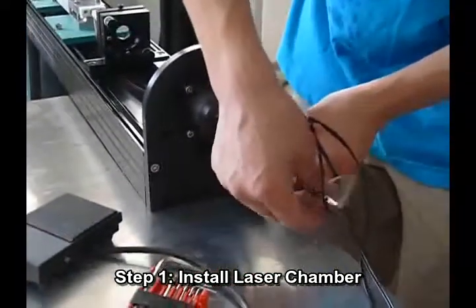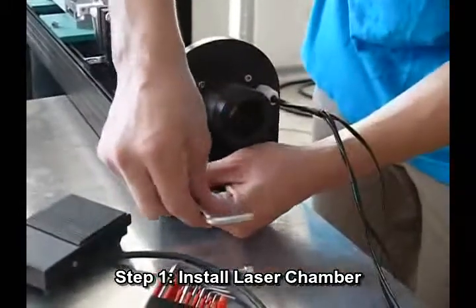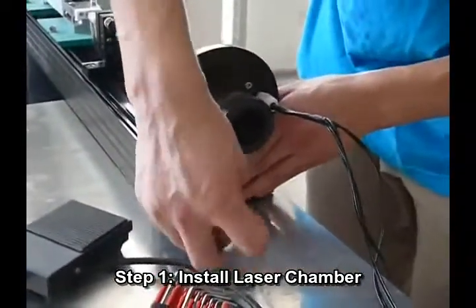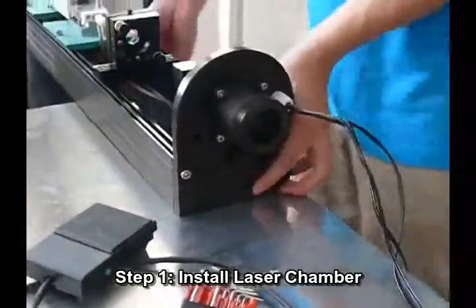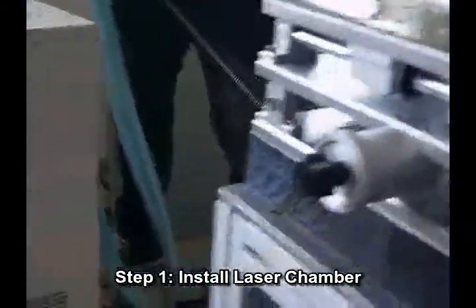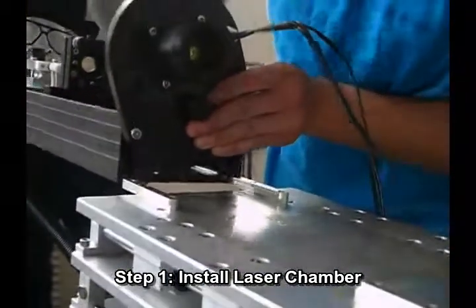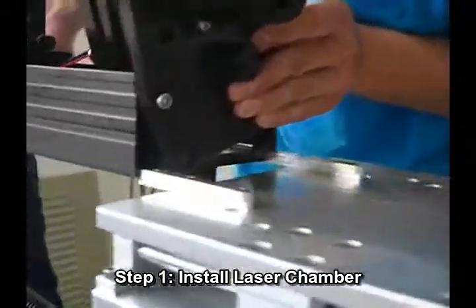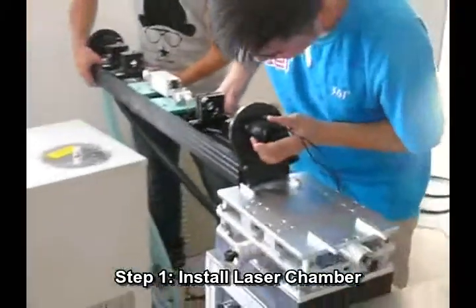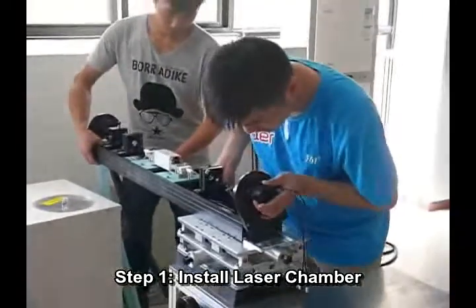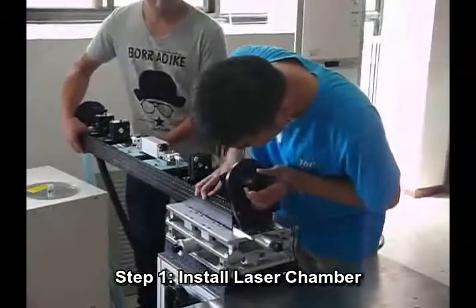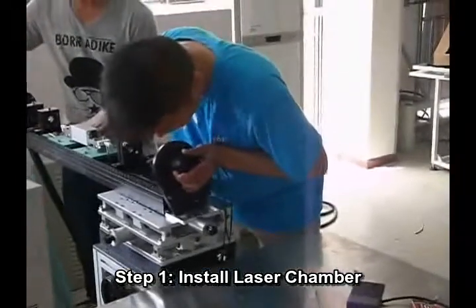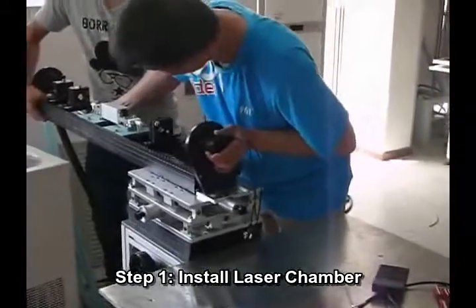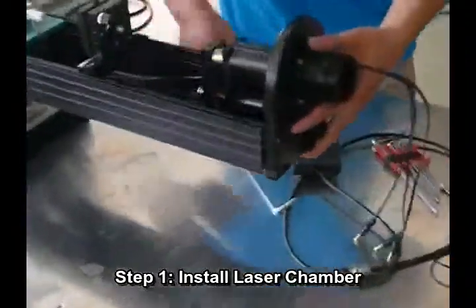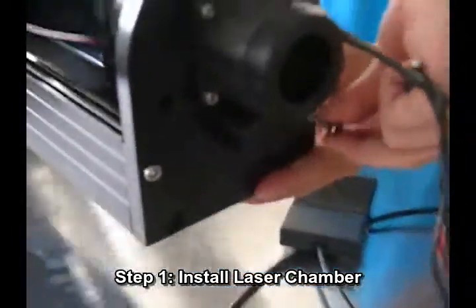Now let's see how to install the whole system when you receive the machine. Step 1. Install laser chamber. Loosen the 4 screws on the top of laser chamber, just as our technician did. Embed the chamber into the slot and push it towards the table. You might need a hand to do this job. When you find the chamber in a suitable working position, tighten the 4 screws you just loosened.